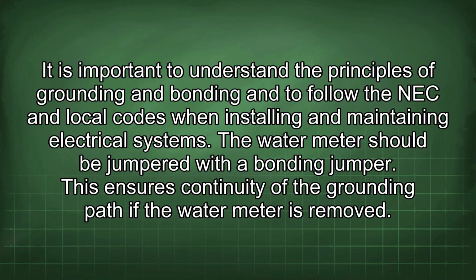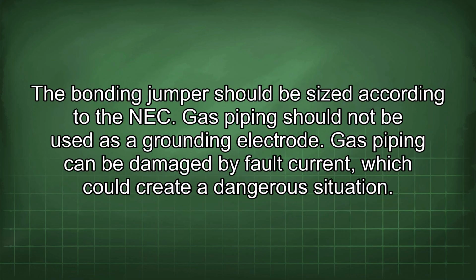The water meter should be jumpered with a bonding jumper. This ensures continuity of the grounding path if the water meter is removed. The bonding jumper should be sized according to the NEC. Gas piping should not be used as a grounding electrode. Gas piping can be damaged by fault current, which could create a dangerous situation.